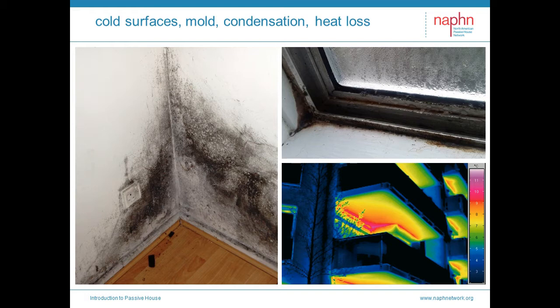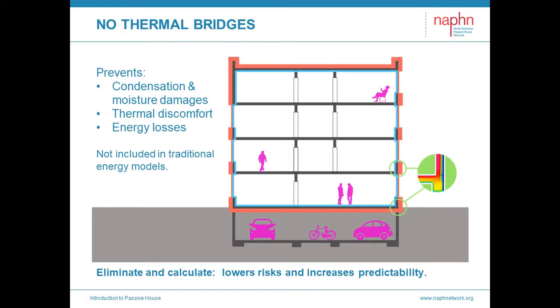The colder interior surfaces can cause condensation, as we see on the window frame at the upper right and mold on the left. To overcome them, typically we overheat — we're treating the symptom with brute force. With passive house, we avoid the problem in the first place. Thermal bridges typically occur at junctures where the floor meets the wall, or wall meets the roof, or at window frames meeting walls, balcony connections, and structural connections. The energy loss causes thermal discomfort, condensation, and moisture damages.